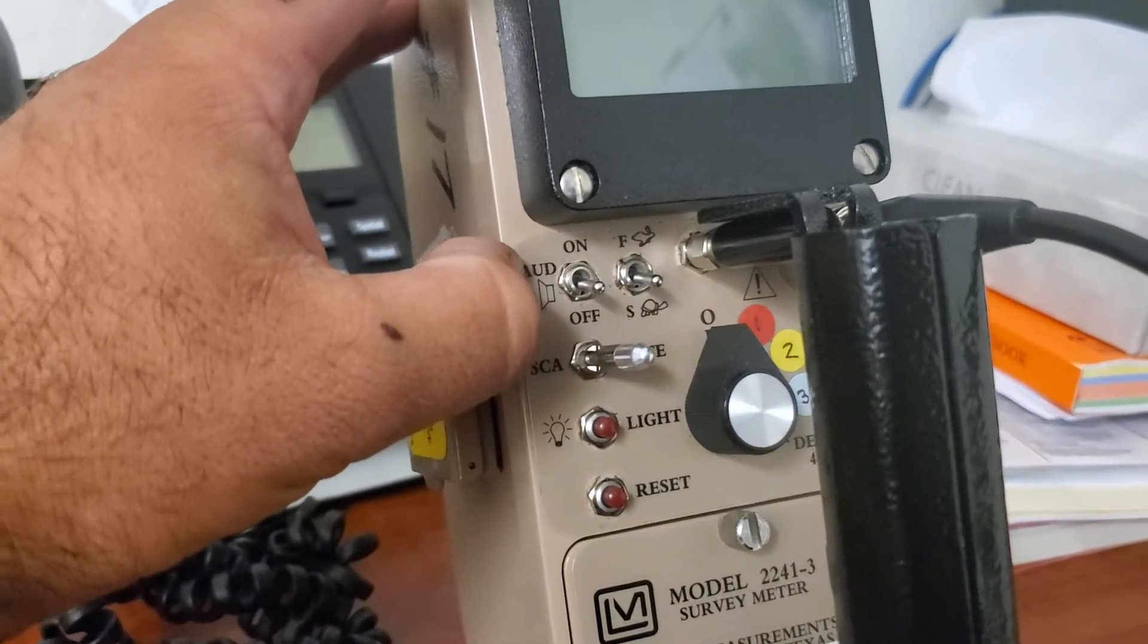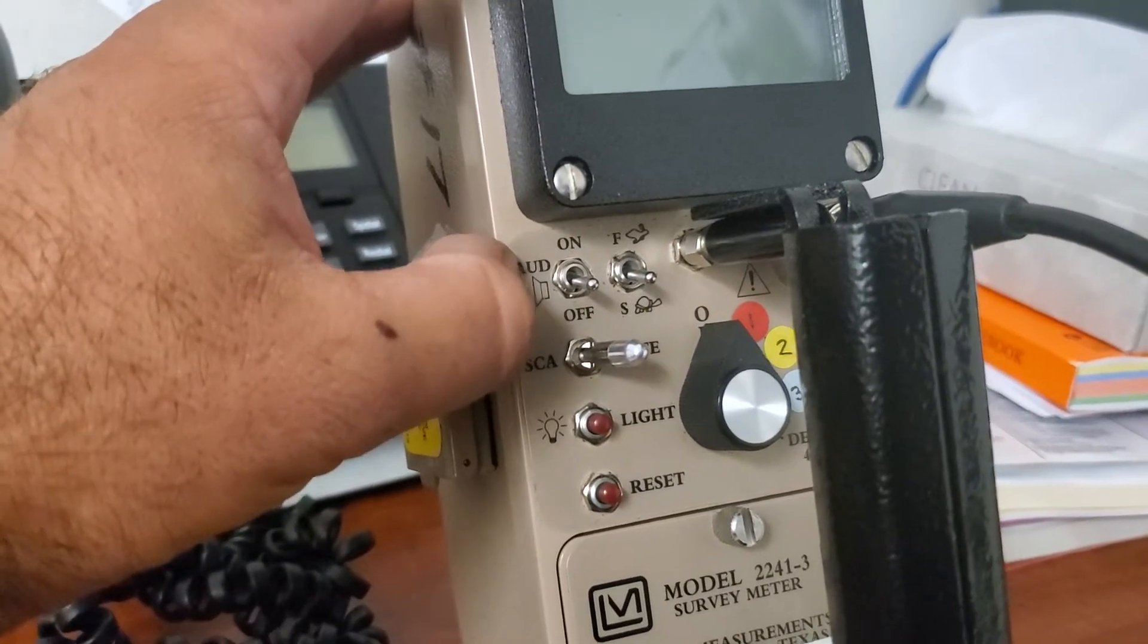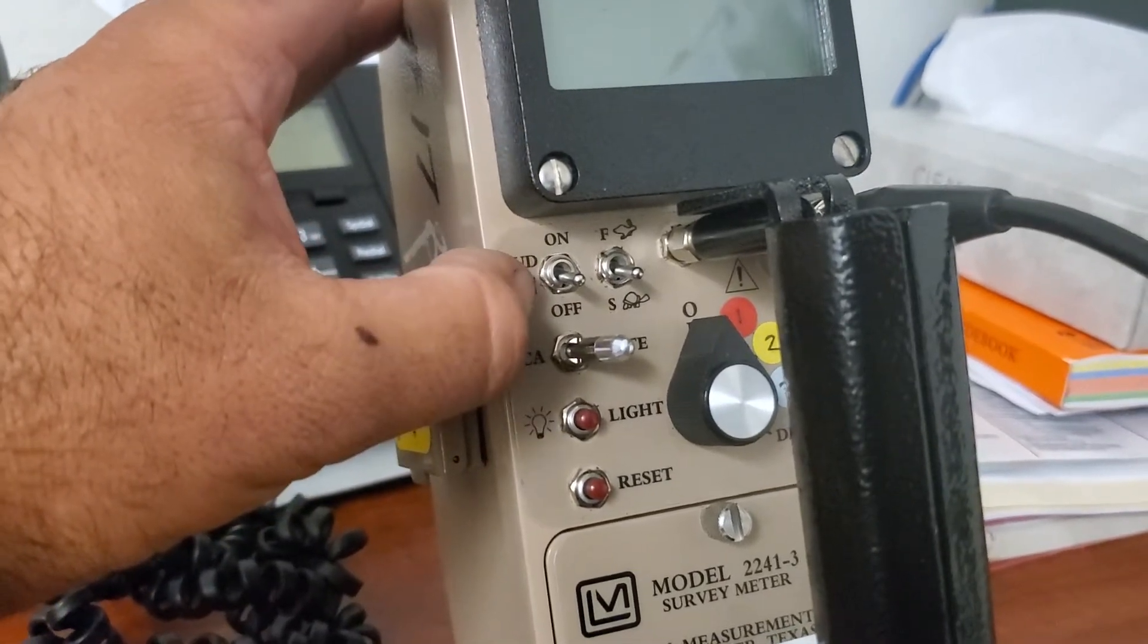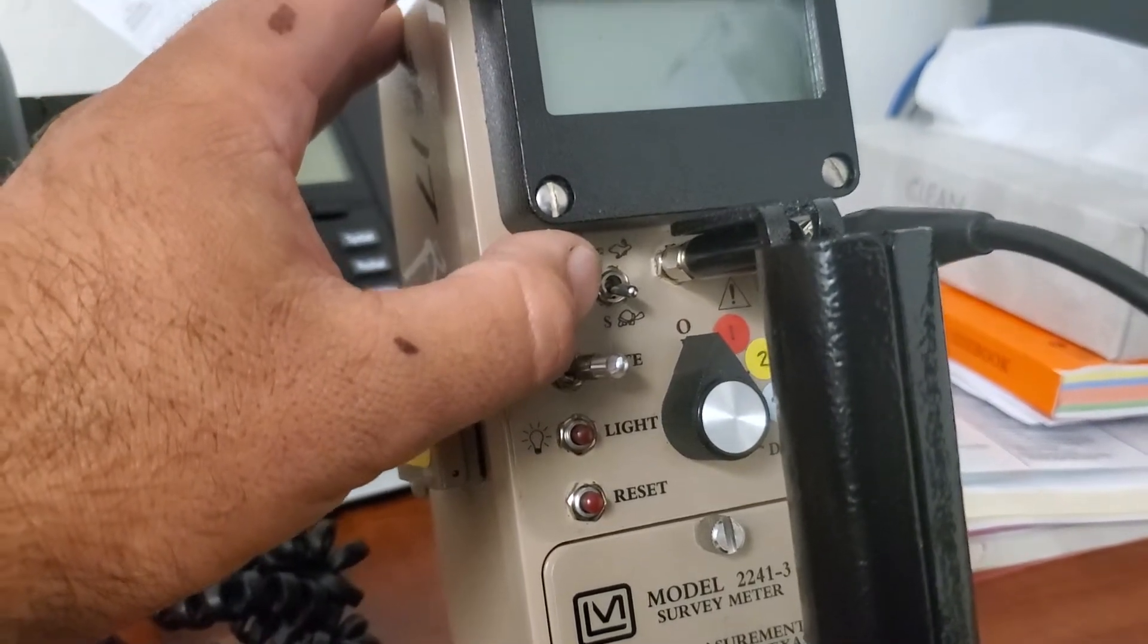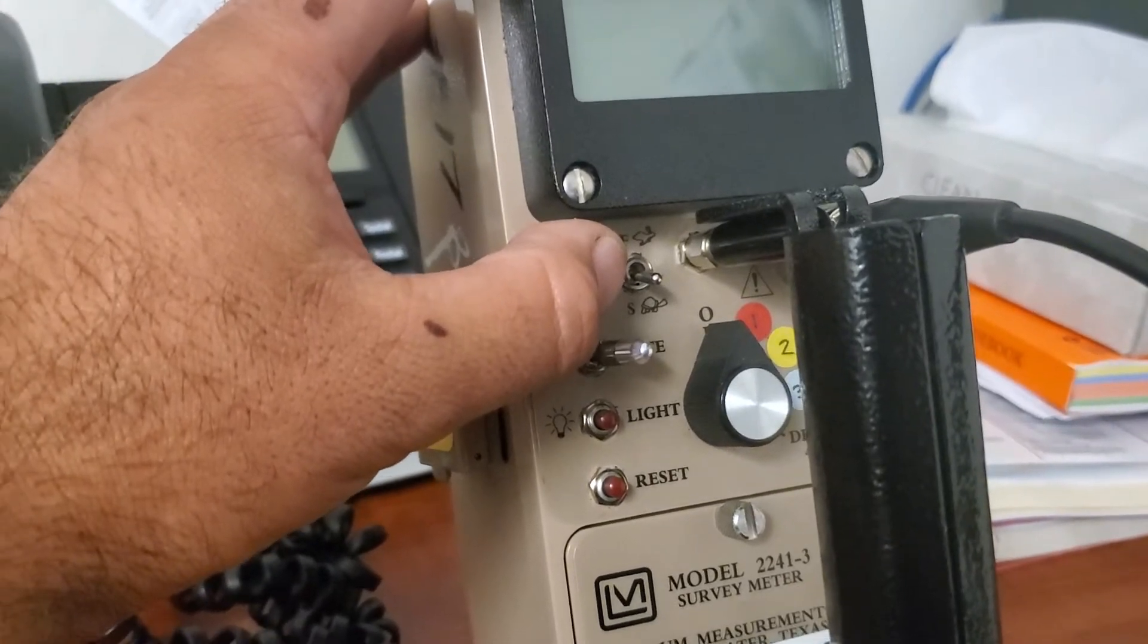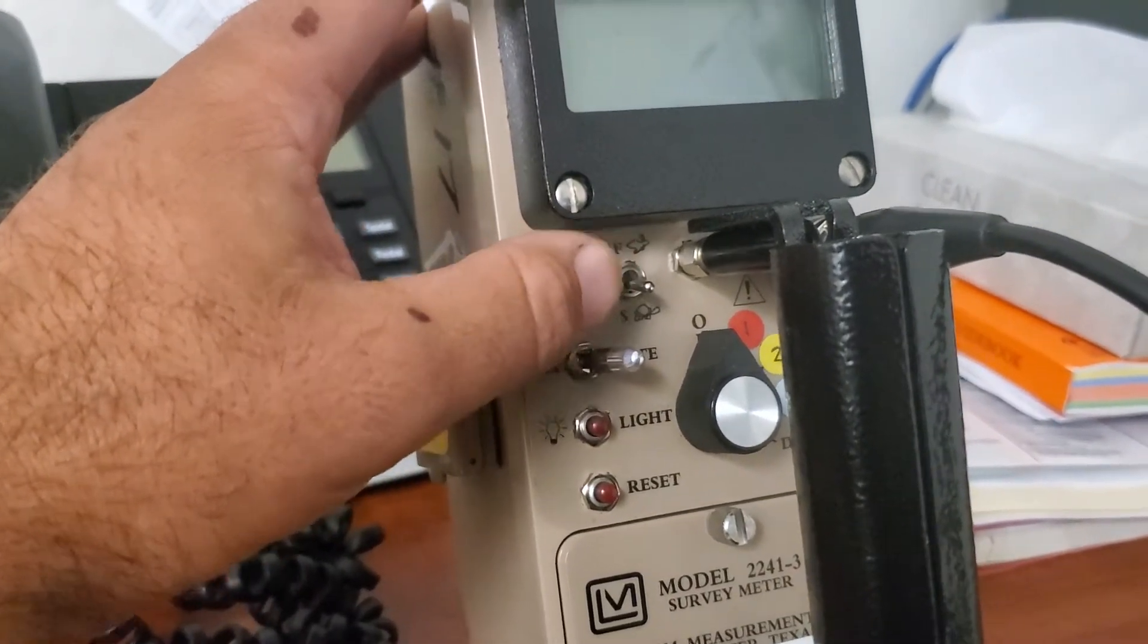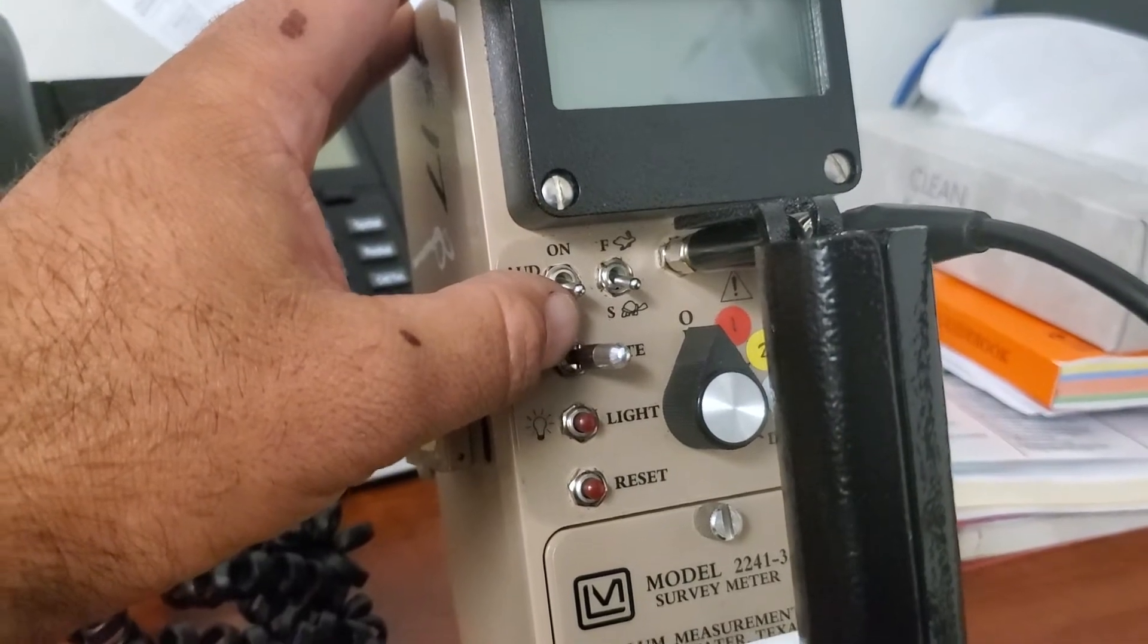What that does is it will break through even the off setting. So even if you accidentally toggle it off and you're getting into something that's a little hot, that alarm will break through. The first alarm is called an alert and the second alarm is actually an alarm.